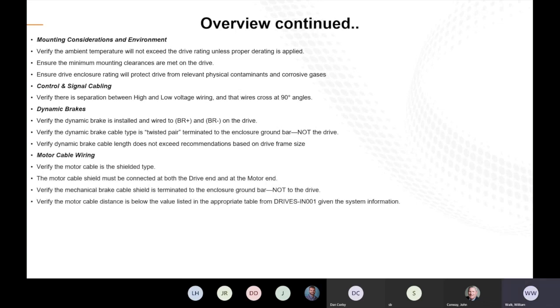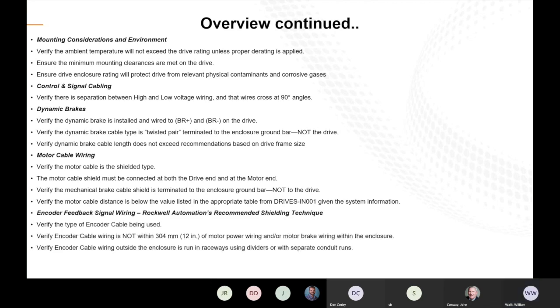Motor cable wiring, again, ensure that we're using the proper wiring from your drive to your motor. And you might not need shielded cabling for this. It's all just going to depend on the distance from your drive to the motor. And with your encoder feedback signaling, like I've said before, just make sure you're using the shielded cabling. Keep your wiring separate from your high voltage lines.